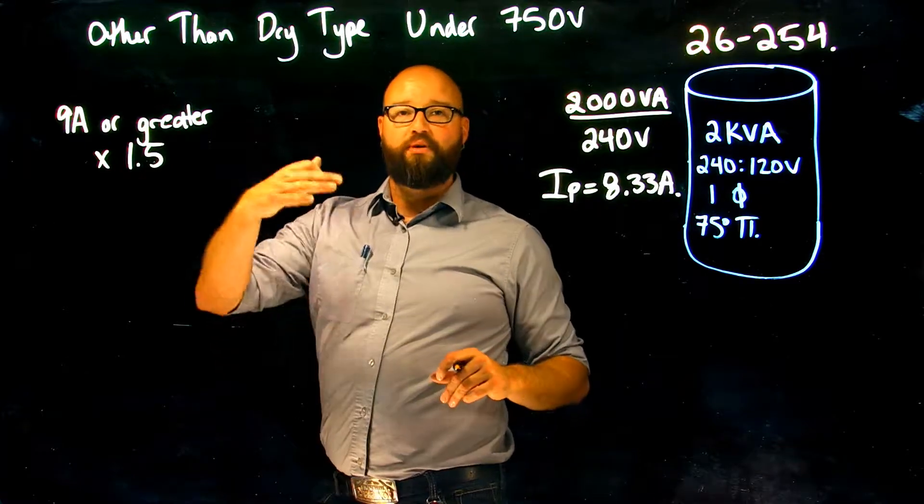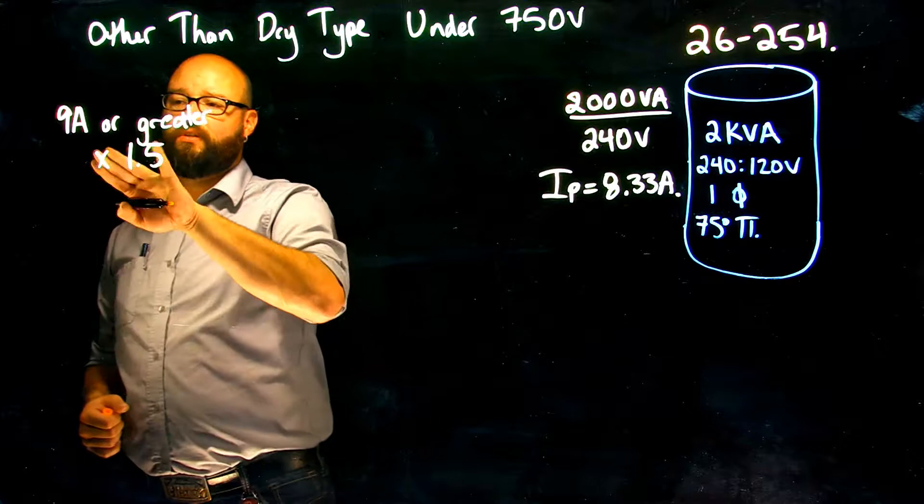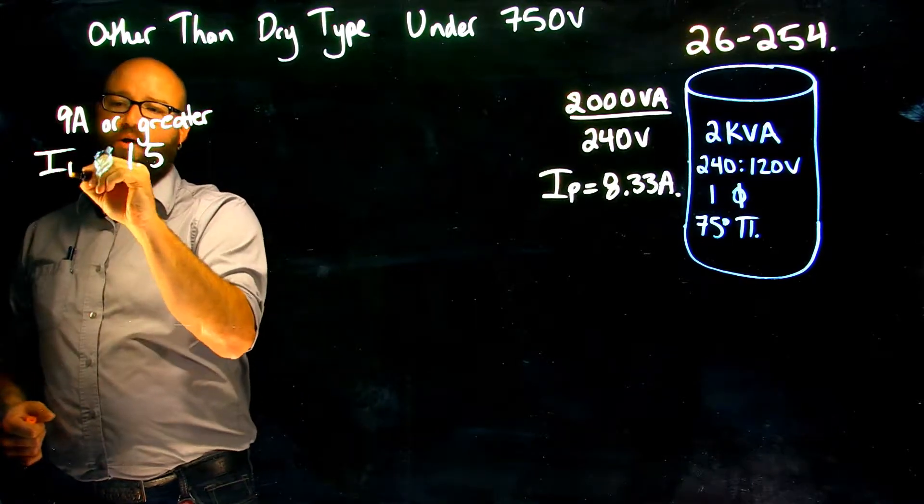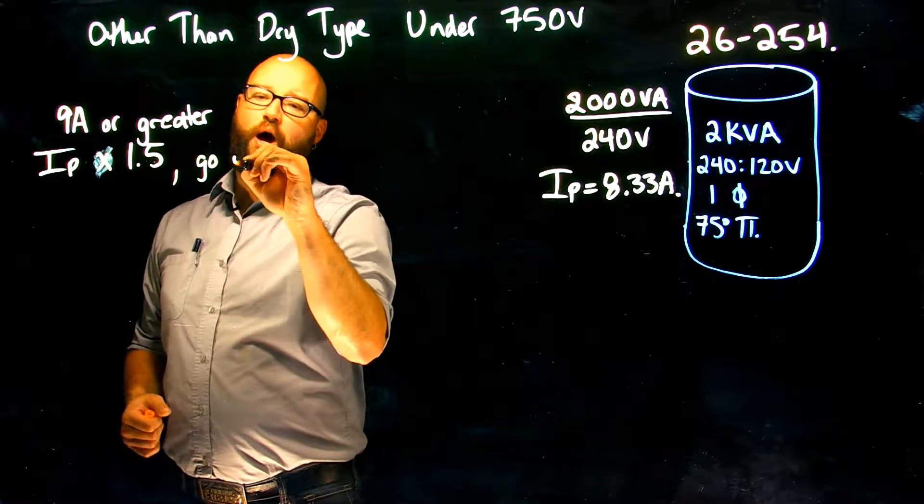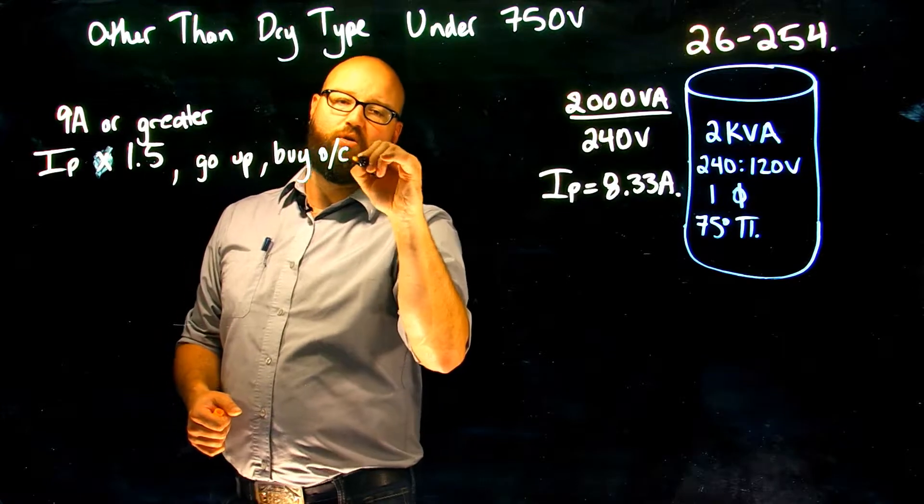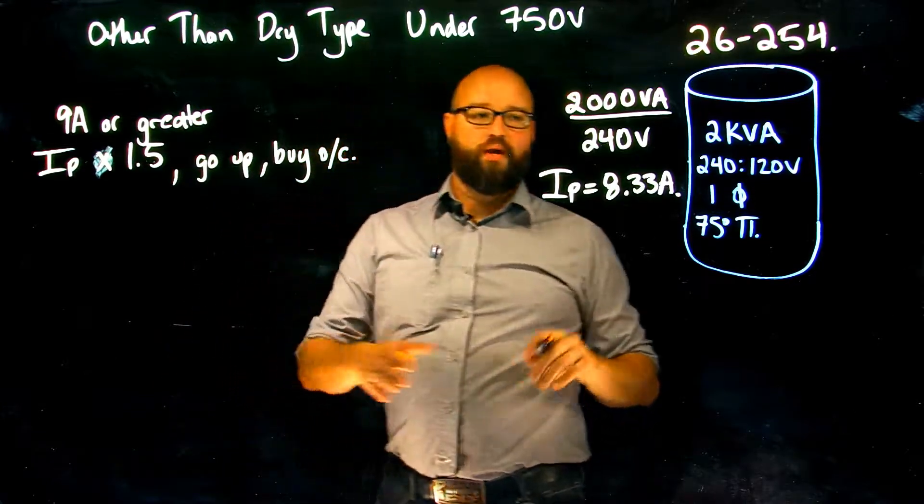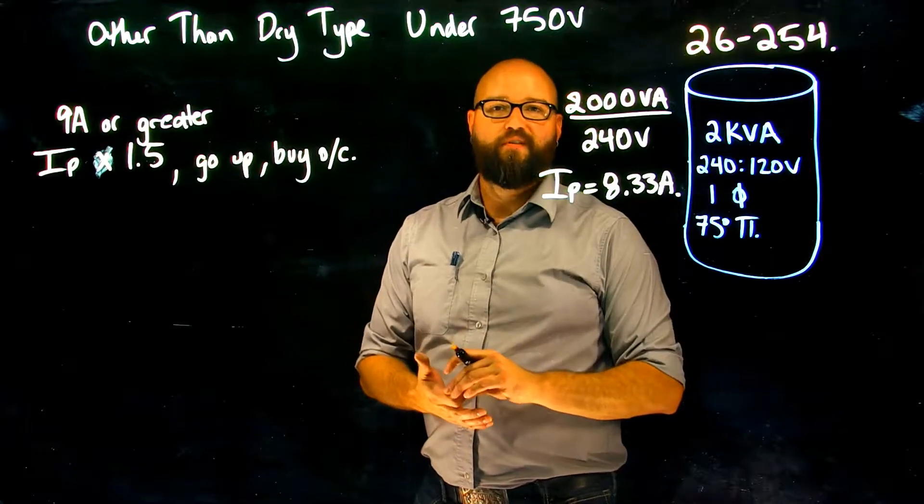And if we read further on, it tells me if that size is not available I am allowed to go up and select the next available size. So times 1.5, so I primary times 1.5, go up, buy overcurrent.